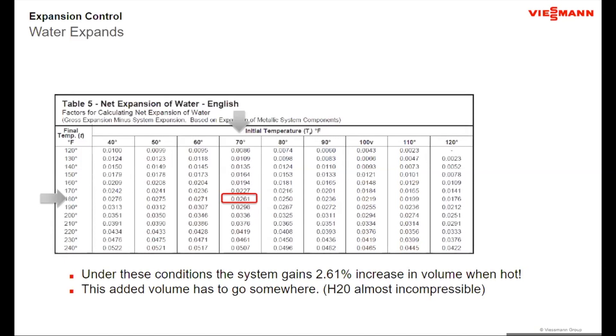When it comes to expansion tanks, it's about purpose versus function. The expansion tank accommodates the water, and the real reason for it is to keep my closed system closed. If I don't accommodate the water, the relief valve — which is a safety device — will open and let water out. So when I size the expansion tank, it's not just about giving expanded water somewhere to go; if it's properly sized, the relief valve on the system doesn't lift. That's the ultimate goal when designing a system.